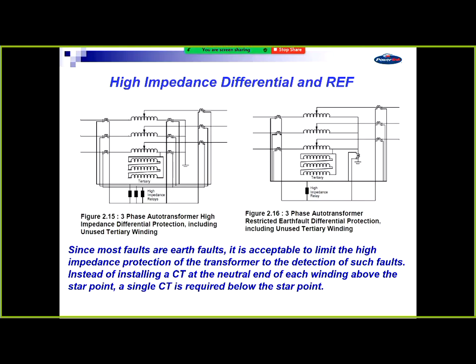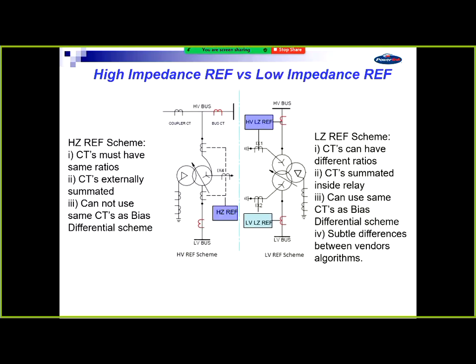So that's one that we do use at times, that restricted earth fault, a high impedance. We sometimes use a low impedance, which is not as sensitive, but we can do that within the bias differential relay. So we use the same CTs as that, so it's a bit more wiring into the relay. That's what the schemes look like.